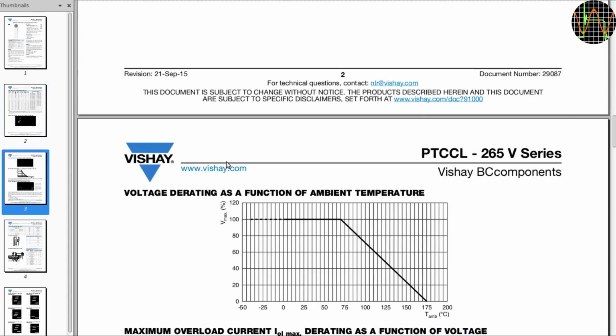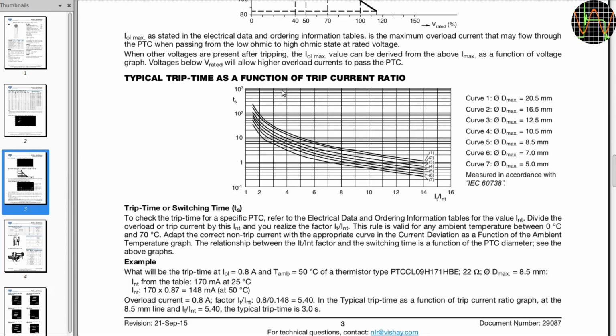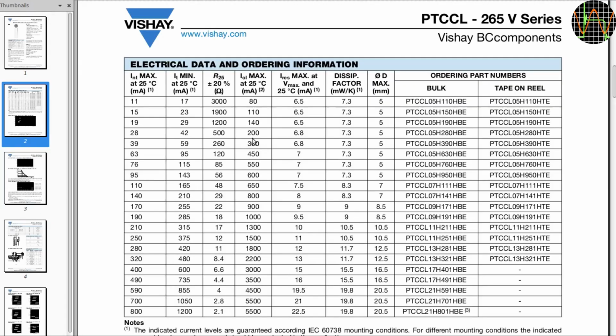With this data, we move to the graph of typical trip time as function of the current ratio. For the first candidate, we look up 5.4 and check against curve 7 for 5 mm diameter. It should trip within 1.5 seconds or so. For the last candidate, it's 1.9 against curve 6 for 7 mm, which looks like around 15 seconds, which would be far too long. The others are somewhere between these, but I think 1.5 seconds is a good value, hence I picked this one. Let's examine it more.